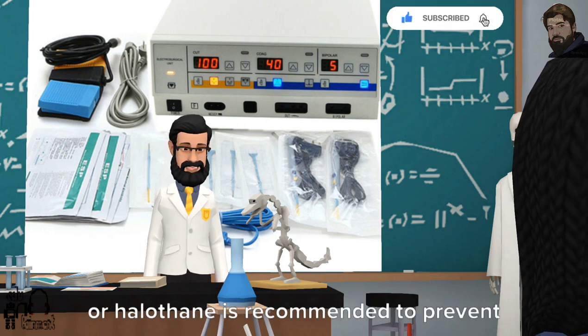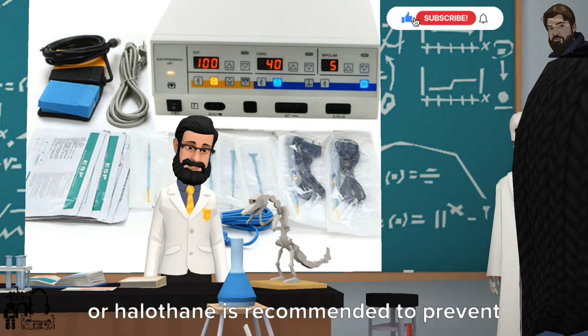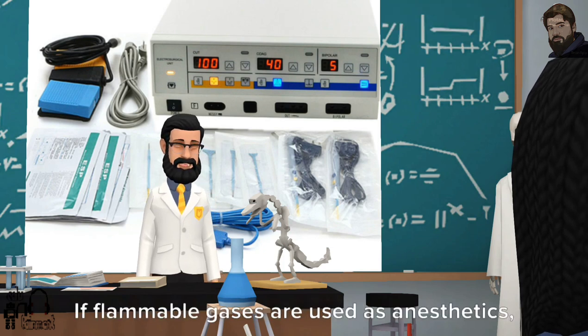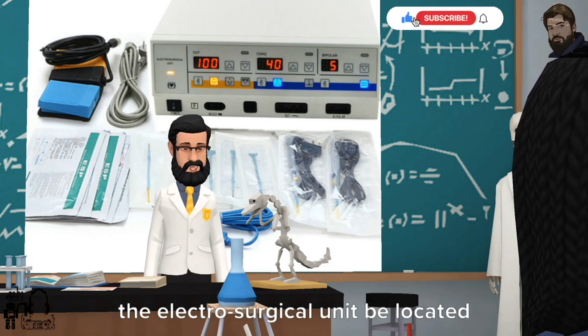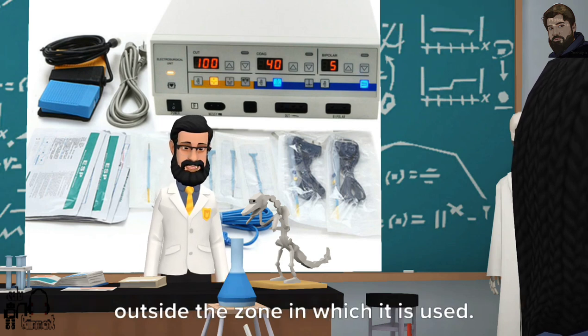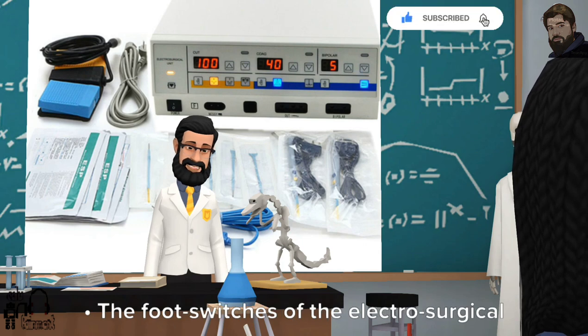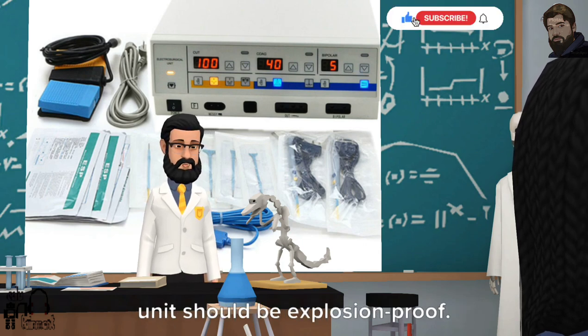The use of non-explosive anesthetics such as nitrous oxide, fluorothane, or halothane is recommended to prevent sparks. If flammable gases are used as anesthetics, the electrosurgical unit should be located outside the zone in which it is used.